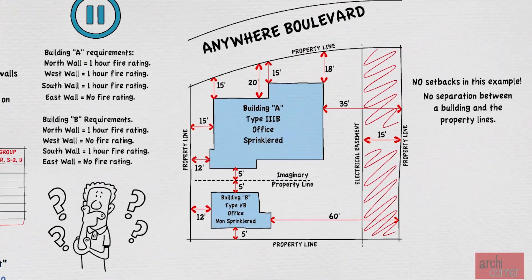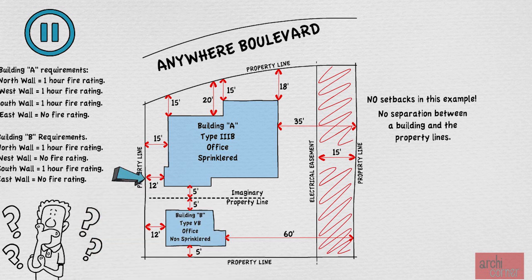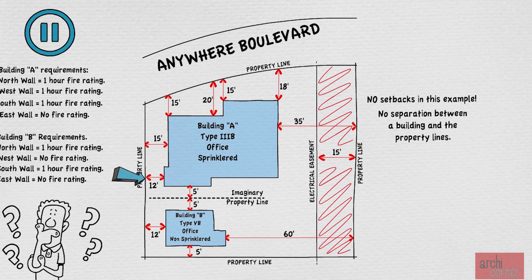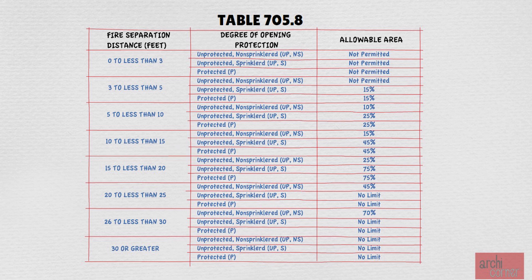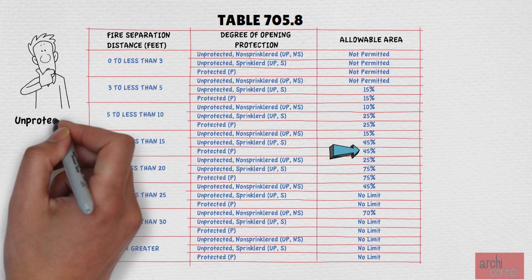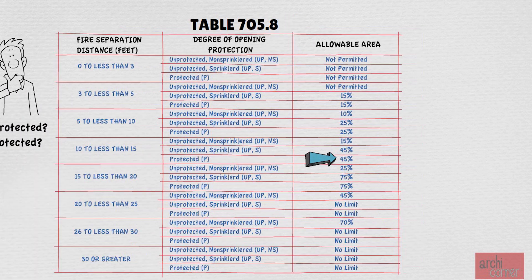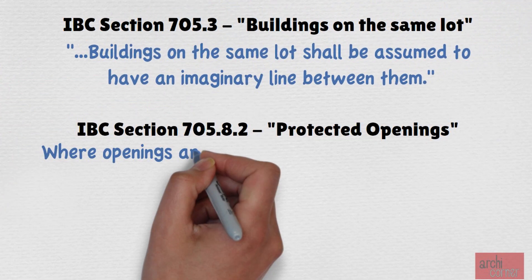To make sense of this, let's start with Building A and analyze the west walls. The distances between the building and the property line are 12 feet and 15 feet, and the building is sprinklered. Let's start with the first section that is 12 feet away from the property line. The chart tells us that if a wall is between 10 to less than 15 feet and the building is sprinklered, we are allowed to have 45% of our wall provided with unprotected openings. Even if the openings were protected, per the table the allowed opening percentage would still be 45% of the wall.